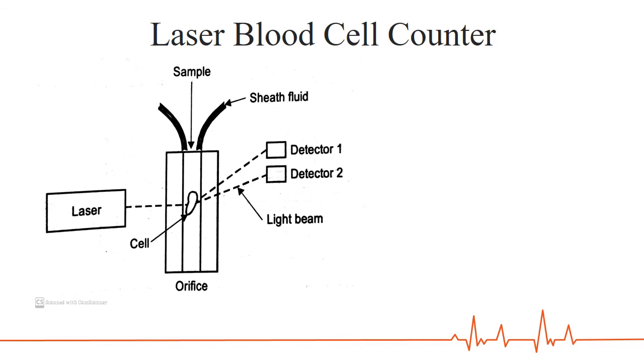Now, the blood cells are illuminated by the laser light and they scatter light. The scattering angles of platelets and red blood cells are having large difference so that the scattered light from these two types of cells are directed into two different photo detectors. The output of the photo detector is given to a properly calibrated digital voltmeter which gives the density of red blood cells or the platelets.